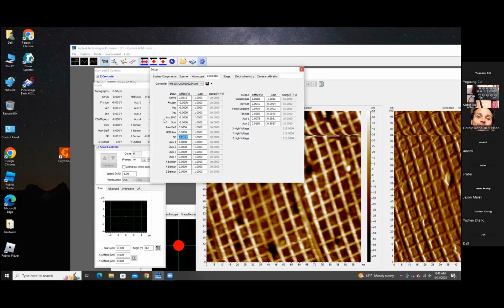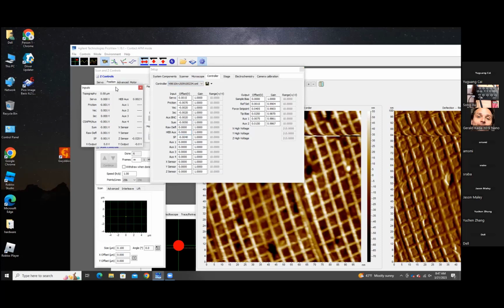Yeah, it's supposed to be 0 because there's 0 input basically. Yep, we could spend time on it, but we can move on. So the next step would be to go to your controls drop-down dialog again. Advanced. This time we're going to look at your outputs. And we're only going to look at the sample bias output just for time saving at the moment. But if you go back to your breakout box, you have an output for sample bias. Right now, it should be reading 0 volts. What do you read on your multimeter?